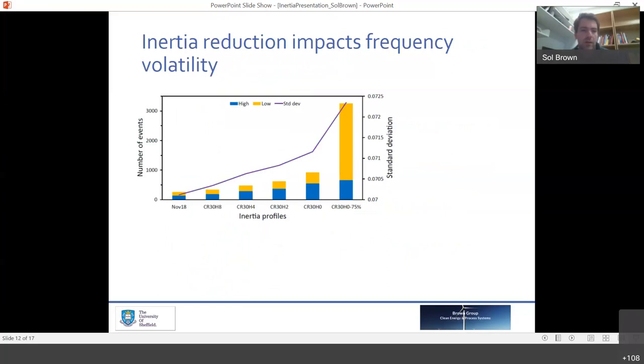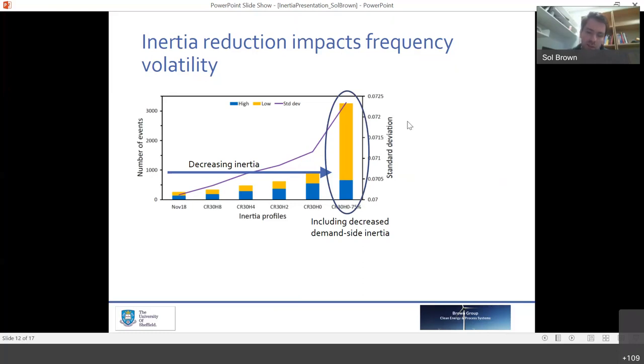If we look at how inertia reduction impacts the frequency volatility in general, thinking back to the curves we saw before with the frequency over time, then we can see that with decreasing inertia from 2018, we get an increasing standard deviation, so an increasing volatility of the frequency on the system. And if we decrease the amount of demand side inertia, then you can see that the low events grow quite rapidly. So this is driven by some of the National Grid scenarios. You can see that we could end up with a greater amount of volatility on the system, and you would want more inertia there to protect that.